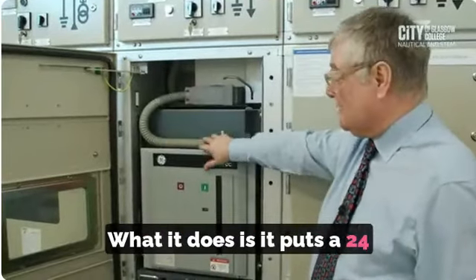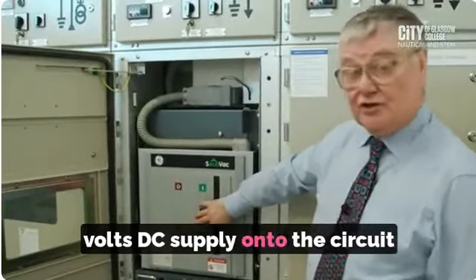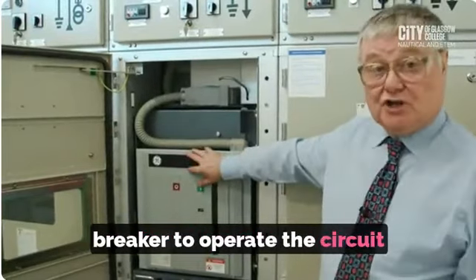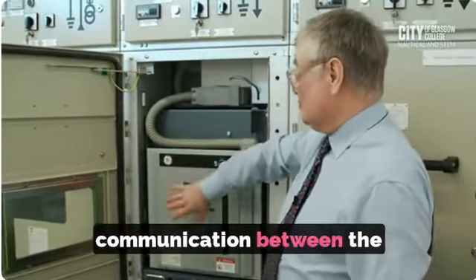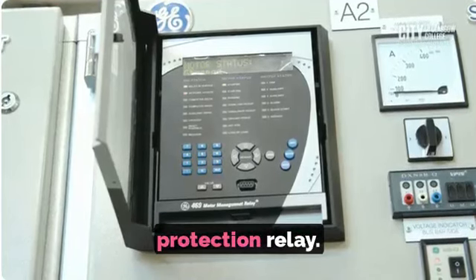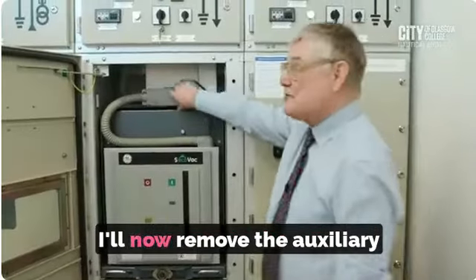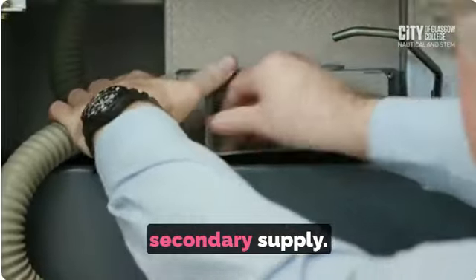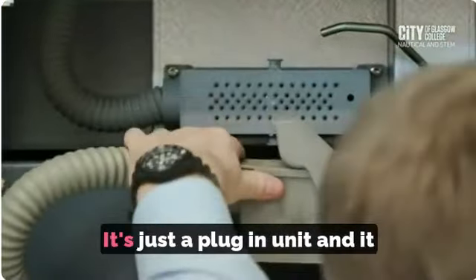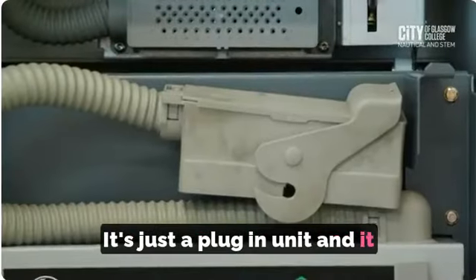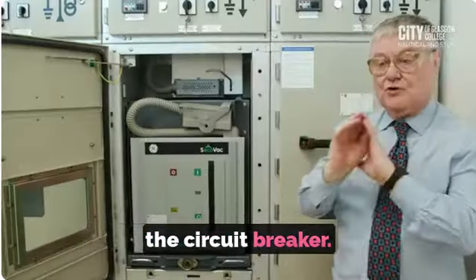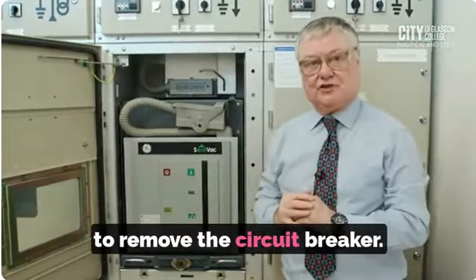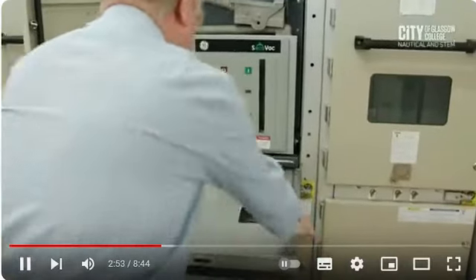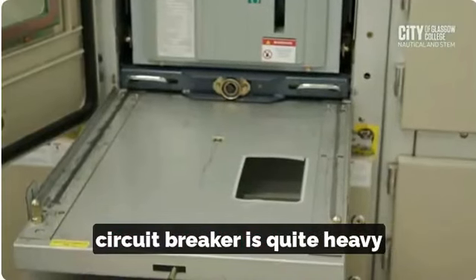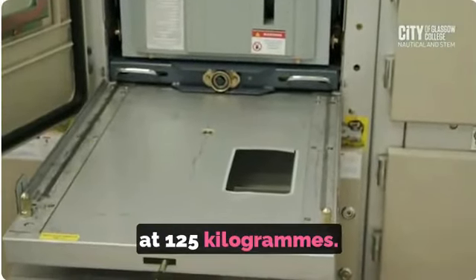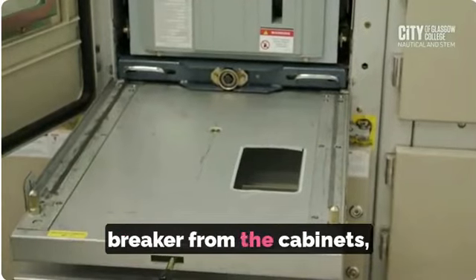We will now remove the secondary supply, or the auxiliary supply. What it does is it puts a 24 volt DC supply onto the circuit breaker to operate the circuit breaker, and it allows communication between the circuit breaker and the protection relay. I'll now remove the auxiliary secondary supply. It's just a plug-in unit, and it affixes to the top of the circuit breaker. We can now bring in the trolley to remove the circuit breaker. A trolley is required because the circuit breaker is quite heavy at 125 kilograms. We will now remove the circuit breaker from the cabinet.